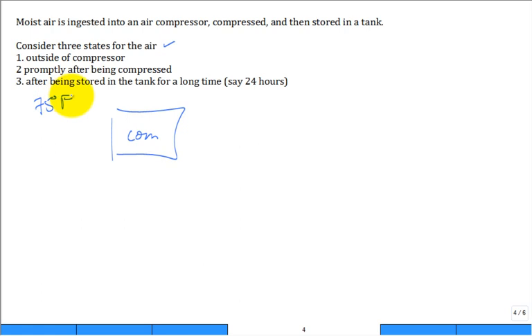Outside the compressor, let's say we have 75°F air and 50% relative humidity. We can get the humidity ratio for those conditions — looking at the psychrometric chart in English units at 75°F and 50% relative humidity, the humidity ratio ω is about 0.008 pounds of water vapor per pound of dry air ingested into the compressor.